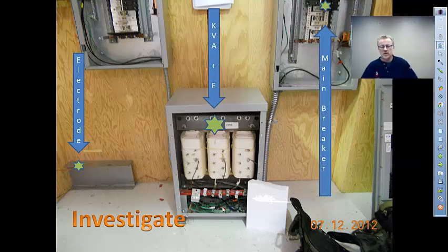You know, the general rule is conductors need to be protected in accordance with their ampacity at the point at which they receive their supply. That's 240.21, general rule. What used to be a batch of exceptions and is now written as permissive language, 240.21(C), the tap rules for transformer secondary, allow us to extend these conductors without protection at their point of supply a limited length. So this breaker is going to be protection for the conductors for overload. Right? Any current in the normal path of current flow has to go through that breaker. The breaker will trip if it's too much.